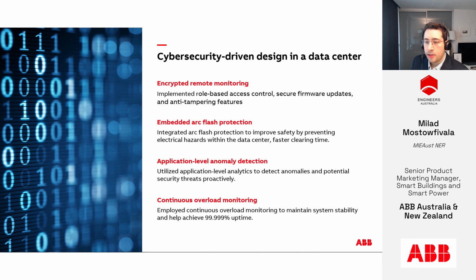Embedding arc flash protection also created a faster clearing time for this client. As you're aware, the data center landscape is constantly moving toward higher current, wanting to achieve higher fault currents up to values of 5,000 to 6,300 amps, so creating a faster clearing time for them is very crucial—another important factor we proposed in this project.